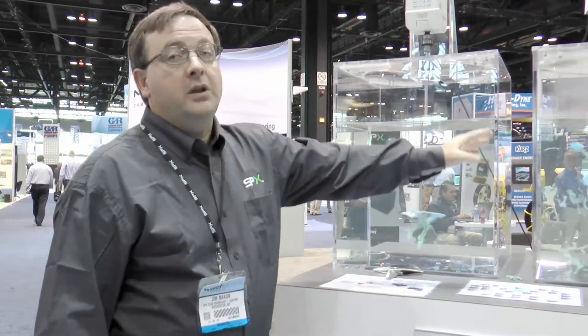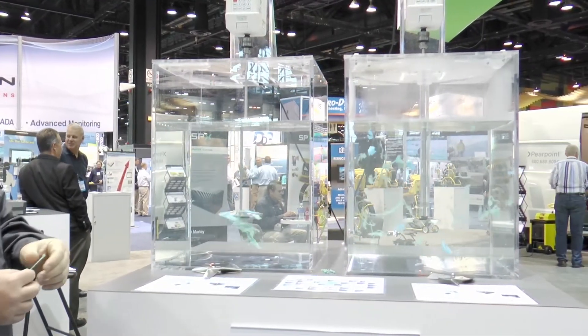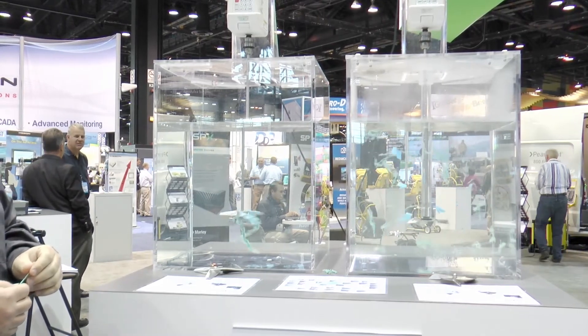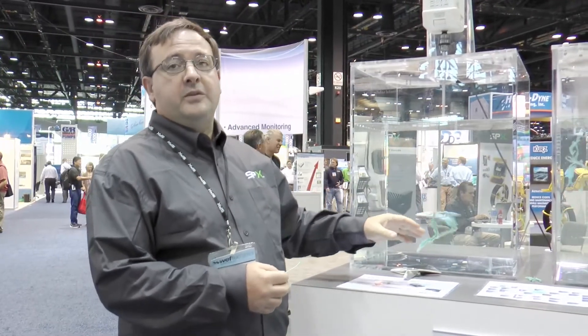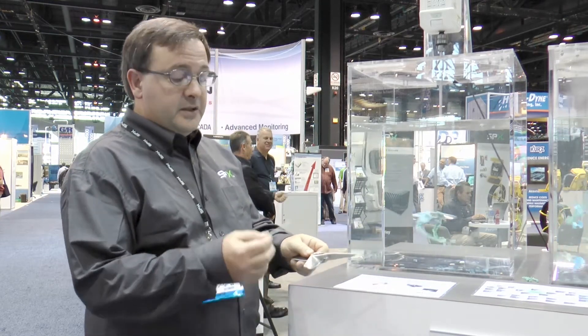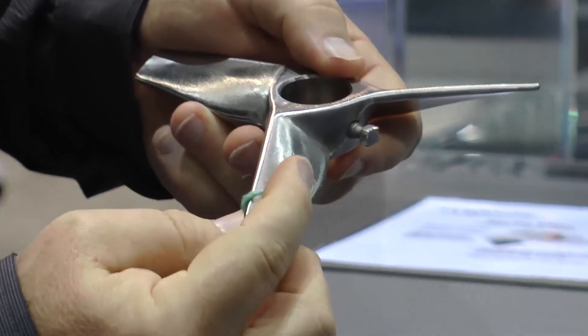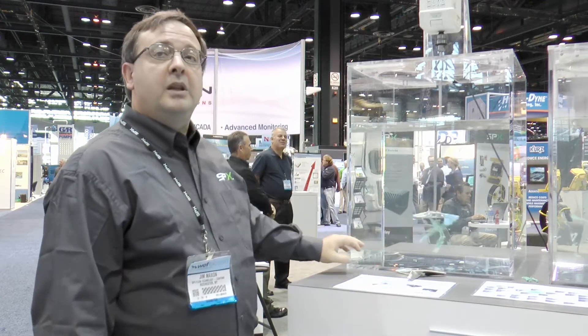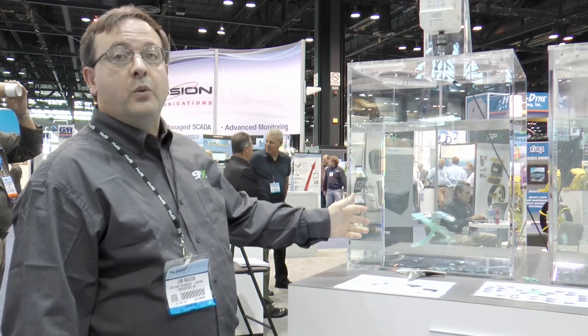Here we have a setup of a side-by-side conventional A510 axial flow impeller and our new clean edge impeller. In this tank and in the other tank, we started out with fibrous material — a typical mop head of about one inch in diameter, one inch in length — and charged both tanks with this material. In this tank, what happens typically within 10 or 15 minutes is that a piece of rag wraps around the tip of the impeller and forms a nucleus. Once that starts, the rag propagates completely across the impeller, and the impeller becomes engulfed with the rag material.